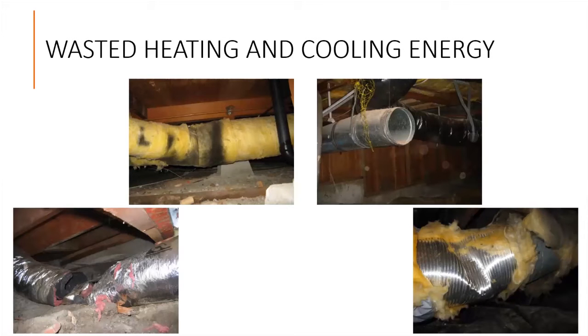We see stuff like this more than you might think. This type of catastrophic failure will lead to enormously high bills, uncomfortable parts of the house, and poor indoor air quality. Those black marks on the yellow insulation are also signs of duct leakage — years of air leaking through and small particles of dust and dirt getting filtered through the insulation. A telltale sign of air leaking near that discoloration.